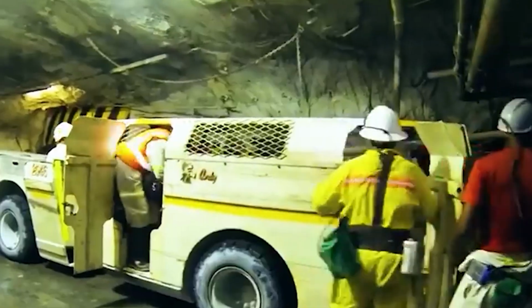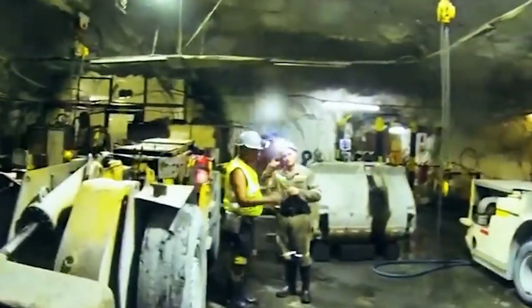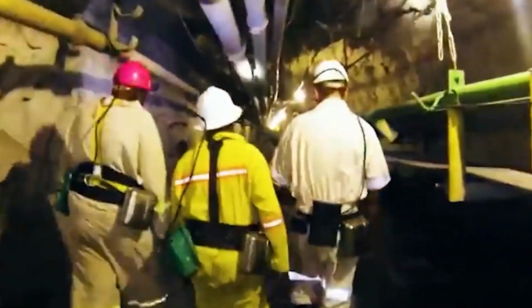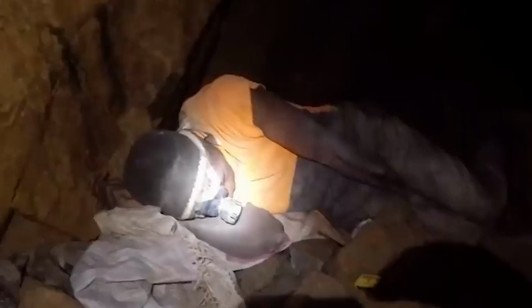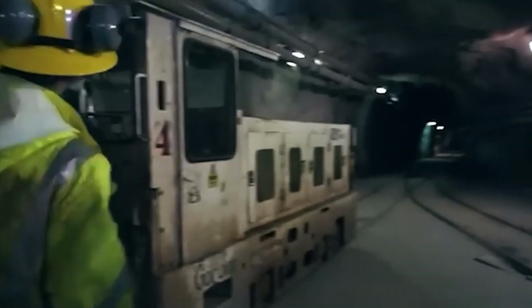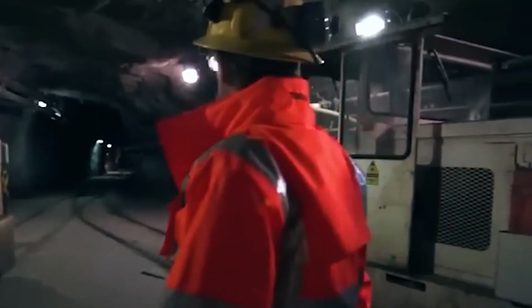The wet bulb temperature becomes the critical measurement that determines whether work can continue. This metric combines heat and humidity to indicate whether human cooling systems can function effectively. High humidity prevents sweat from evaporating, essentially disabling the body's primary cooling mechanism. Mining operations maintain continuous monitoring stations that measure wet bulb temperature and have strict protocols for work cessation when thresholds are exceeded. At these depths, the cooling infrastructure operates at maximum capacity, with slurry ice systems pumping constantly, delivering cooling energy measured in hundreds of thousands of kilojoules per hour.